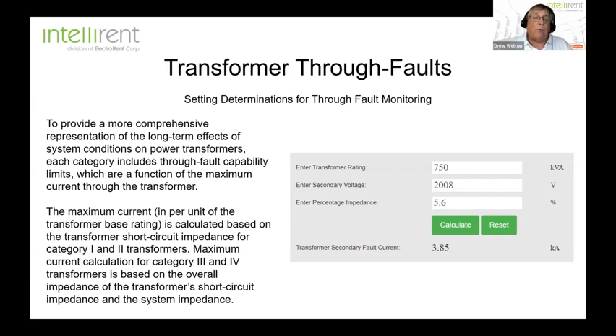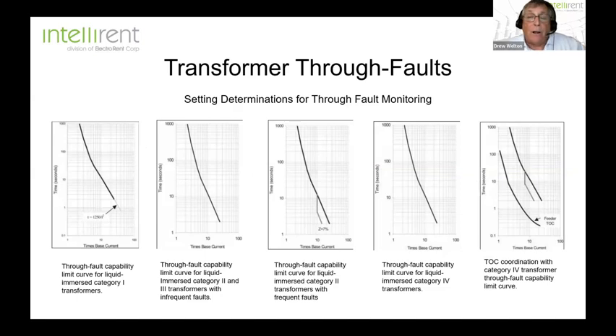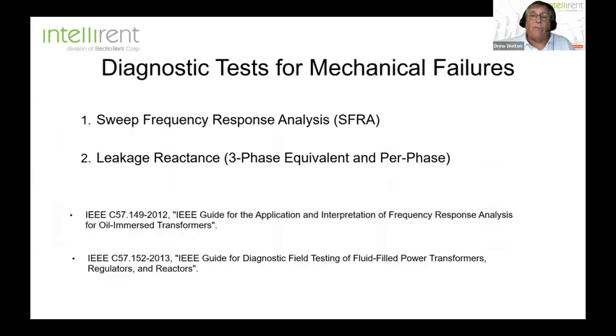So how do we set these through fault monitors? Well, it's not very difficult, really. And you can also always refer to your transformer OEM or your protection engineer that's working on this. But basically, it's just a single calculation of the transformer's rating, secondary voltage, and the percentage of impedance, and this will actually give you a basis for how to set a through fault monitor. And you see, it really depends on what category of transformer it is based on the MVA rating. But you can see that they're all fairly similar in terms of when it's going to alarm, in terms of the time and the times the base current that the transformer is rated for.